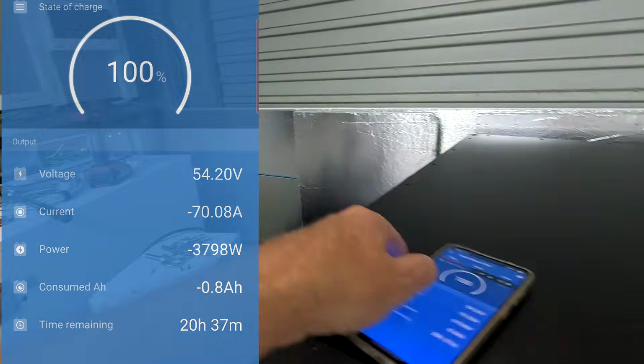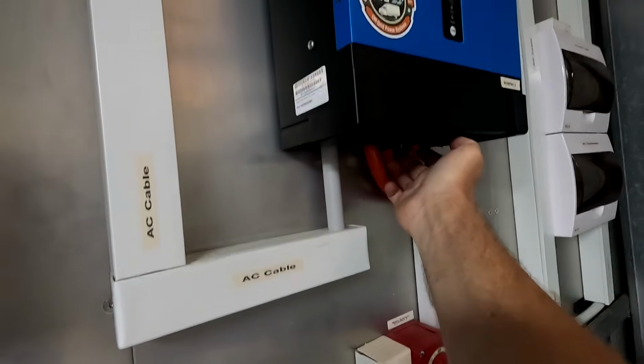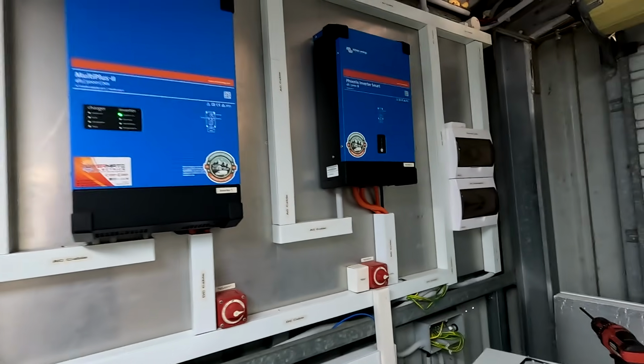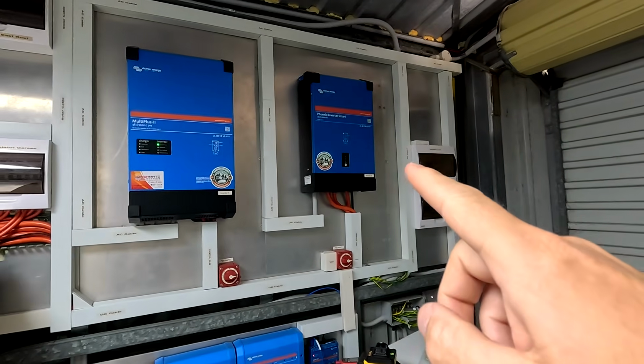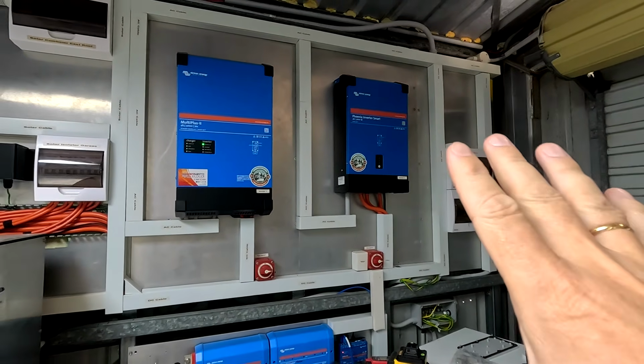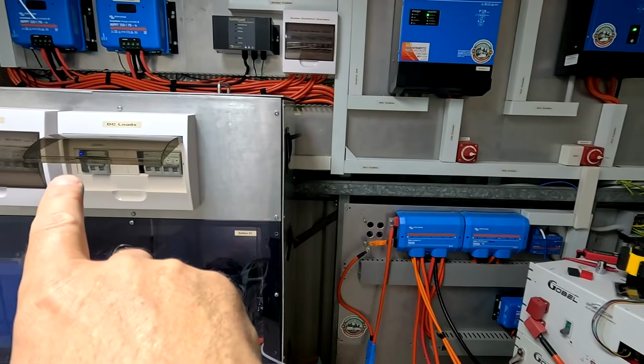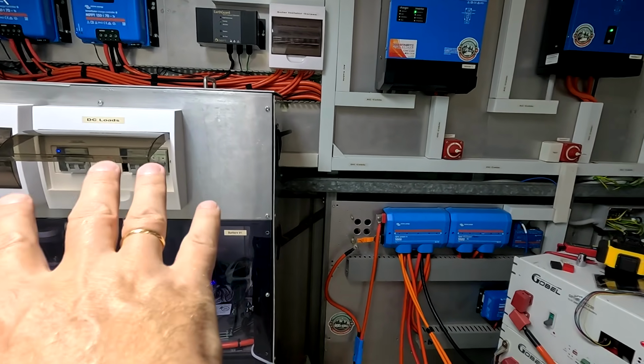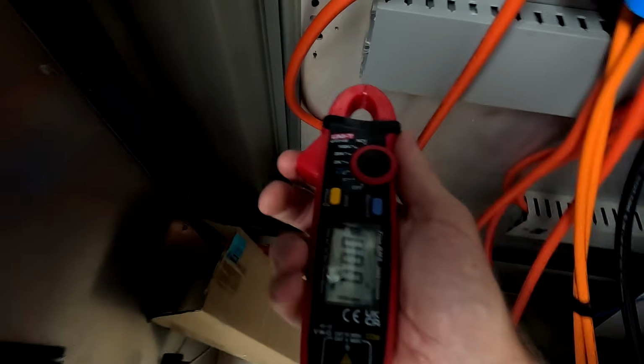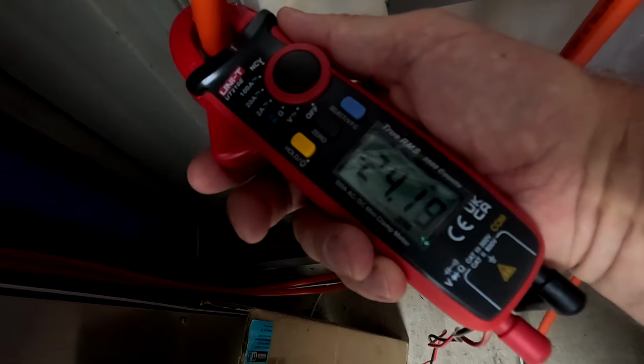So what I will do is turn on this extra inverter, which should kick in. And this should supply around 2 kilowatts directly from the battery through the smart shunt though, but it's not going through the 63 amp breaker bottleneck. So let's measure what is coming. 24 amps only, nice. So we are far under the 63 amps of the circuit breaker.